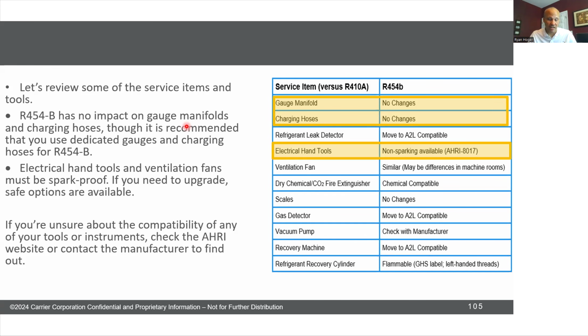For those using analog gauges, you will have to get a new one. No one's going to give you some kind of sticker that you stick in there. You can use your 410A gauges on 454B, but you have to ignore the pink band that your brain is trained to look at. Stop paying attention to that. Only look at the pressure on the outside of the gauge, and then go to the PT chart that I showed you earlier and ask, okay, I have this pressure, what temperature would that correlate to?